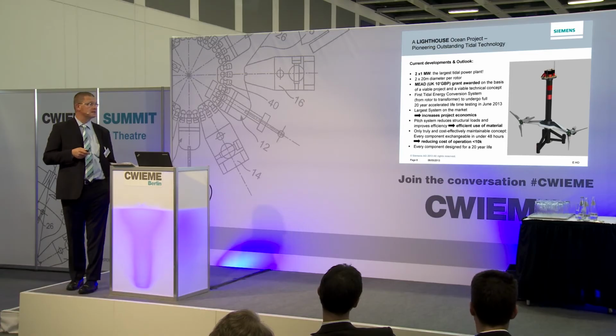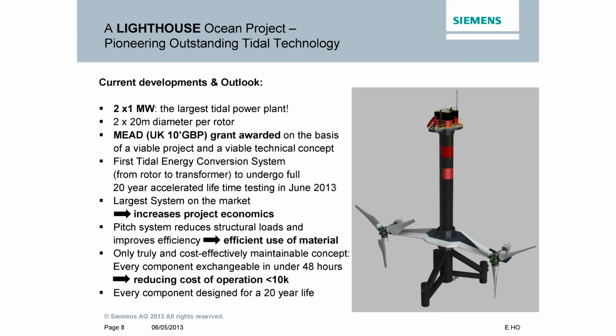We then produce 2 megawatts, one on each powertrain — 1 megawatt, 1 megawatt. Then the pitch starts turning in slightly, as in wind power turbines, so that we only produce 1 megawatt. We don't want to produce 1.5 megawatts when theoretically we could, because the machine is laid out for 1 megawatt. This means it takes the loads of 1 megawatt's energy generation, and we regulate the amount of energy it absorbs out of the potential energy in the water. That helps keep design specifications under check. Otherwise, you'd have to design for a potential 2 to 3 megawatts when you're rarely going to be producing that at any particular site. So that's the pitch system, which works very well on this machine, very similar to wind turbines.